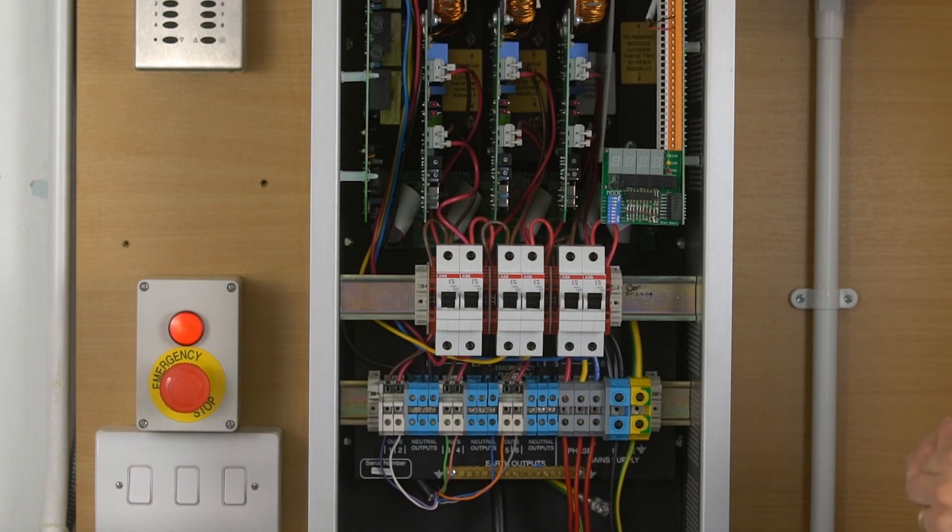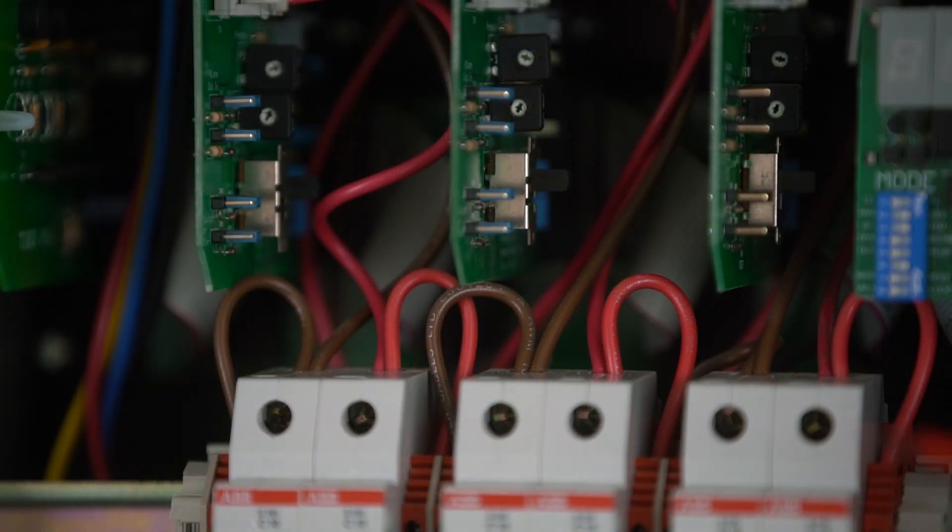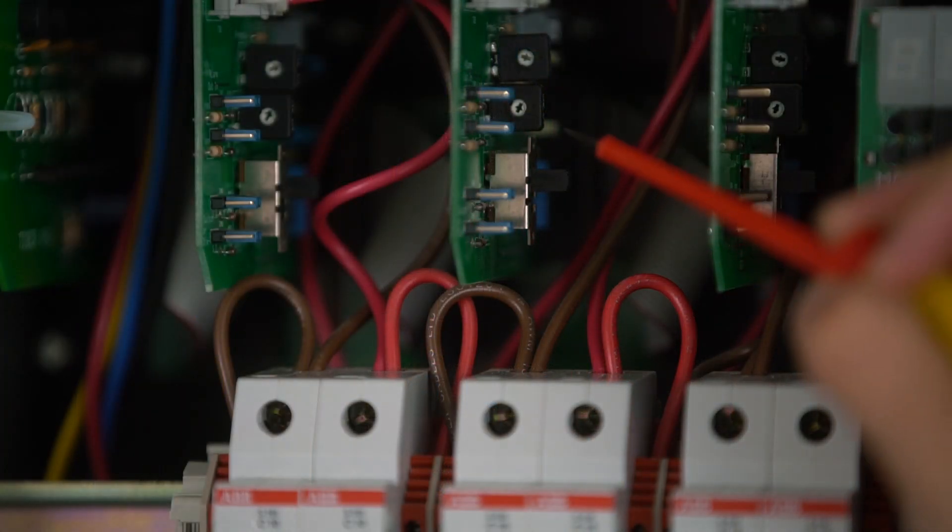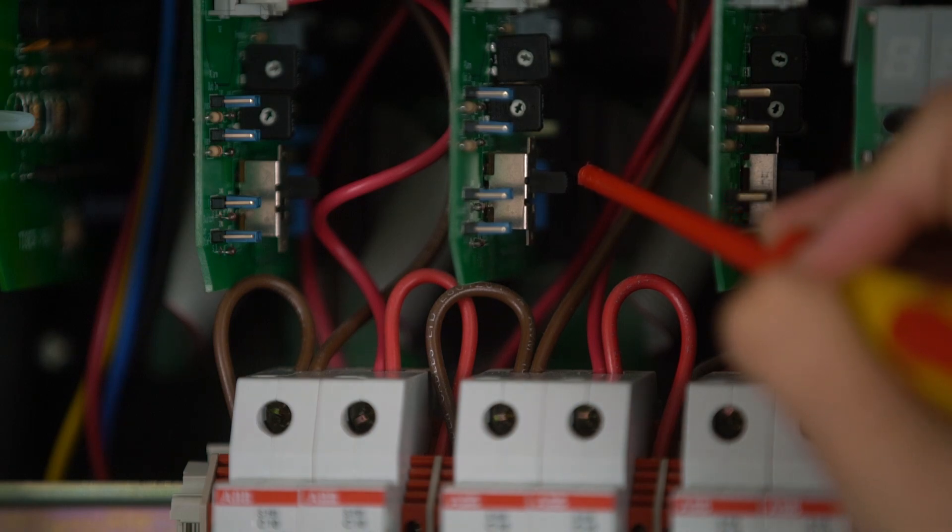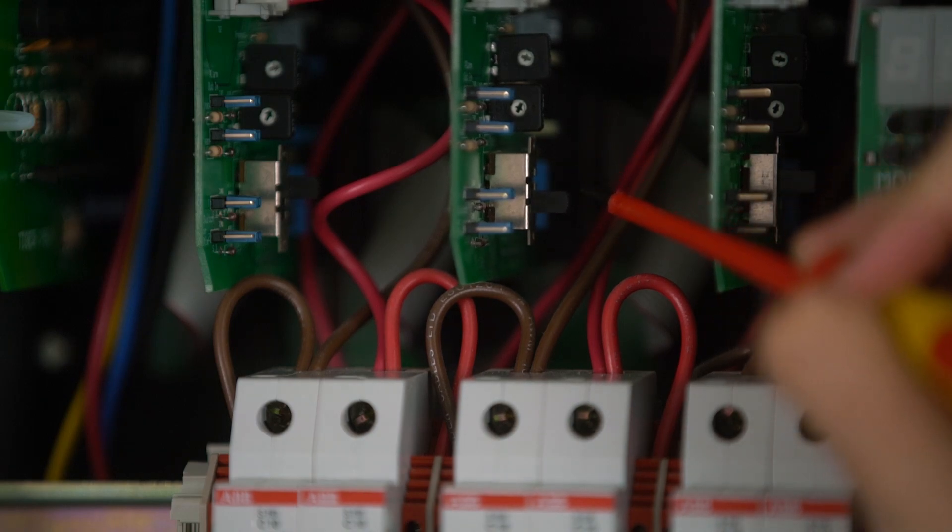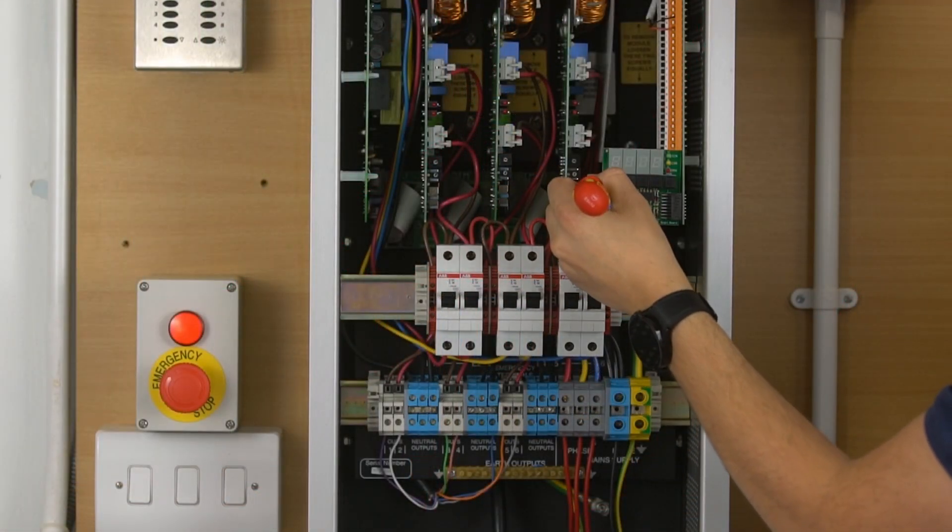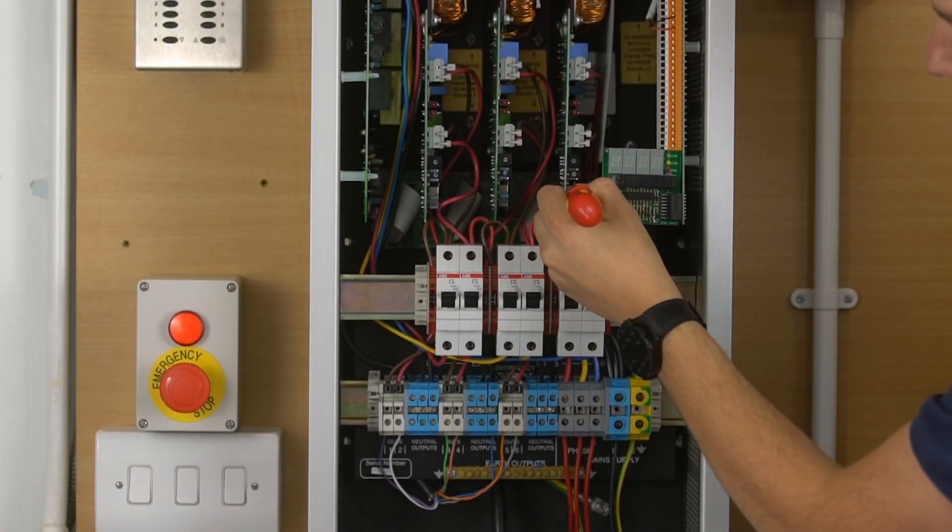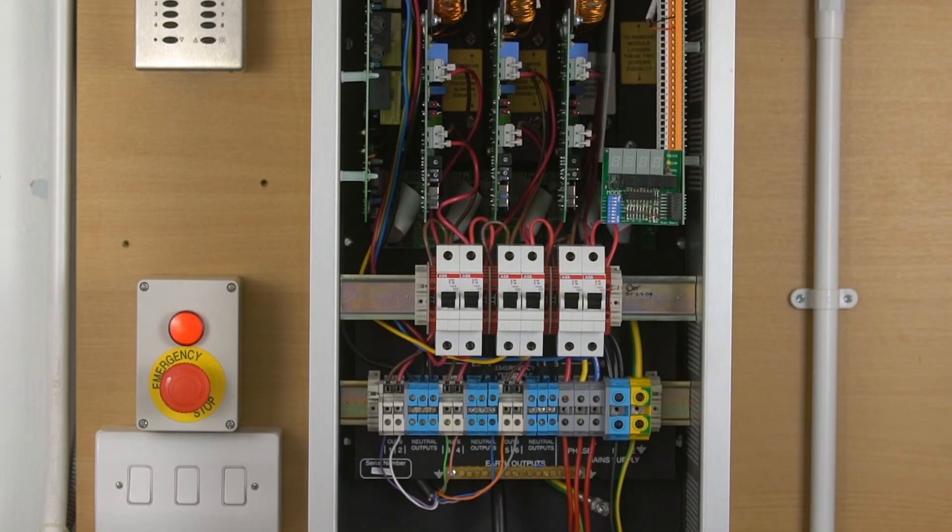To put the panel into a test override mode, you can turn on the test switch on each of the dimming cards. In the down position, that is test, full power out. With this switch down, the keypad will no longer function and the lights will be stuck on.